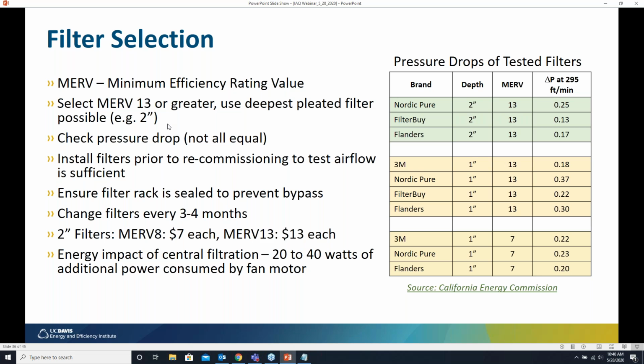I want to point out that you should check the pressure drop of the filters that you are buying. There is a prevailing belief that MERV 13 filters are problematic because of their pressure drop and their resistance, and that a lot of times they won't work in older HVAC systems.